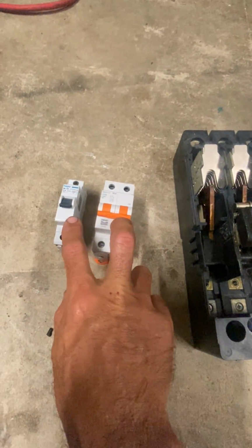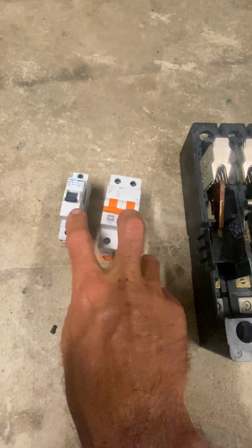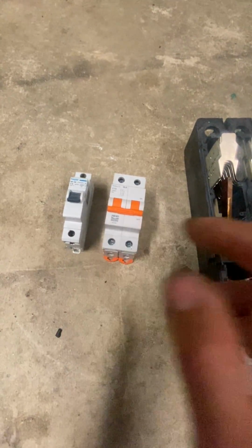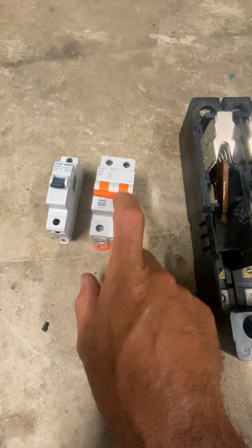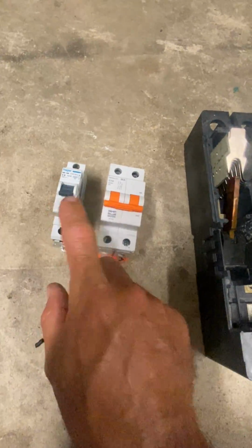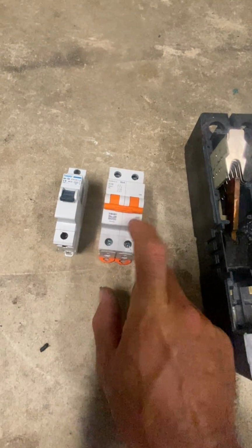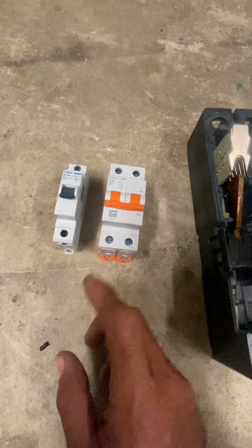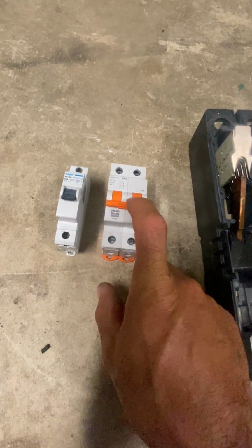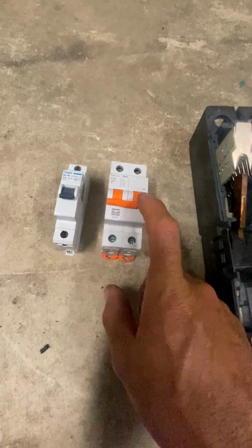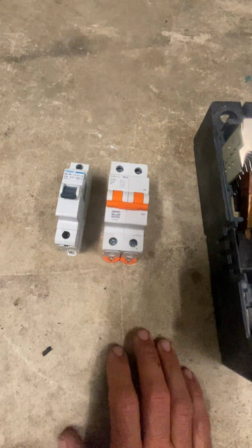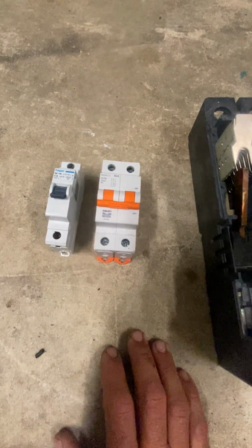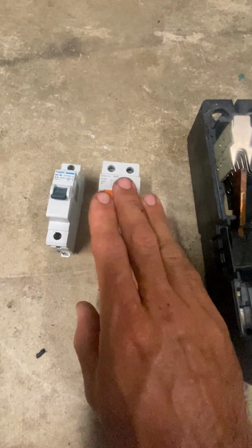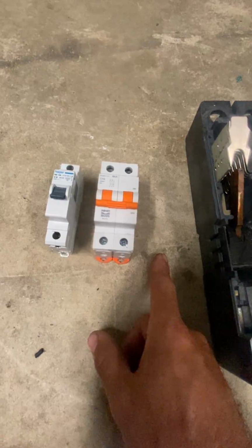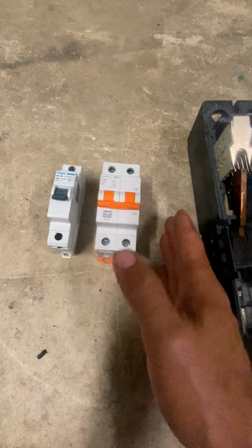And with these guys here, you've got to be very careful if you're using these in a DC application that these are rated for DC operation. To my knowledge, neither of these brands are rated for DC. They probably will work, but it doesn't necessarily mean that it's correct. And if a fault does happen, you may be in a spot of bother, and it may actually cause a fire. I do know that Schneider circuit breakers in Australia are rated for DC operation, and they do some dedicated DC circuit breakers.